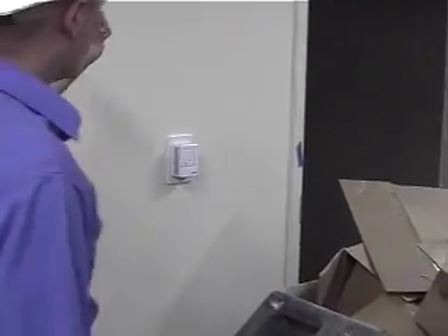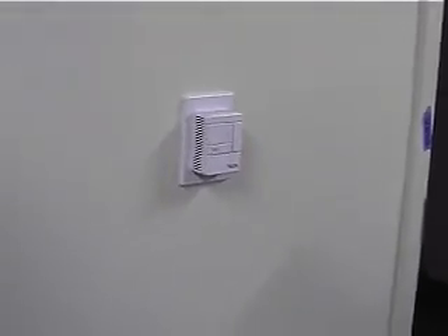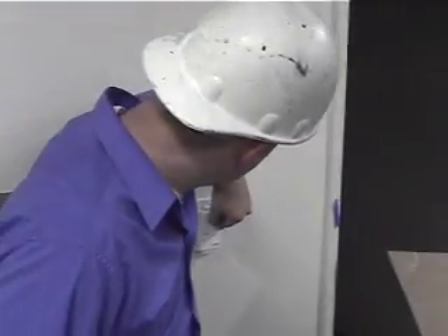Basically, this is just reading the temperature in, and you get it set to whatever. You guys can override stuff so it can't be driven from the slider. The slider can give you warmer or colder, but only if you guys have enabled it. I'm not sure what the policy is here, what you guys do. Typically we have that enabled to like a plus or minus 2 degrees or plus or minus 3 degrees. But you guys can also override it from the front end and say, this is your set point, deal with it. So what are the increments on the slider then, as far as? It's actually set up to go full swing. You can feel it click, click, click, click. Yes. But that's not a specific increment because you could change this range to be plus or minus 2 or plus or minus 3 or plus or minus 5 or whatever. Okay. So it depends on the resolution, on what you put in there.